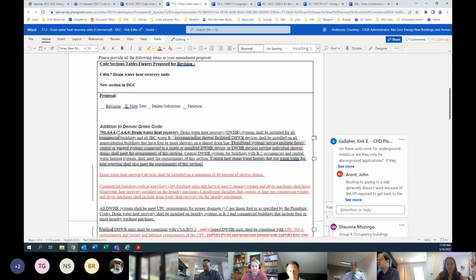Okay yes, so this one we have reviewed before, and there are a number of good comments here. This was a requirement — again, this is Denver Green Code, so it's not the base code, it's an option. But for buildings in Denver Green Code to have drain water heat recovery devices installed on all R2 occupancies or shower facilities, and in all buildings that have 4 or more showers and a shared drain line.